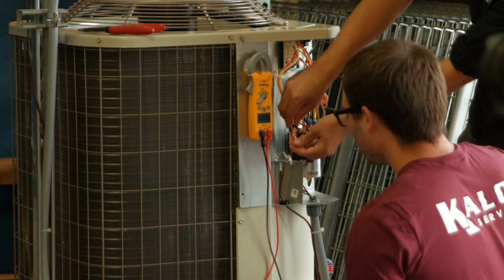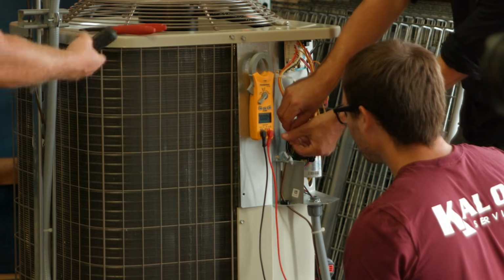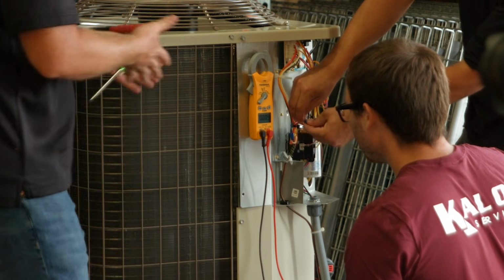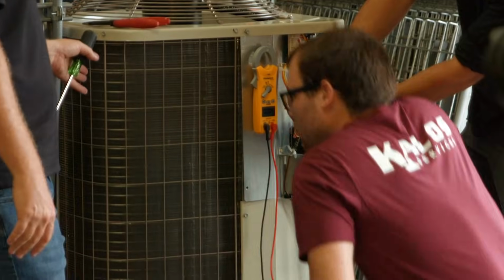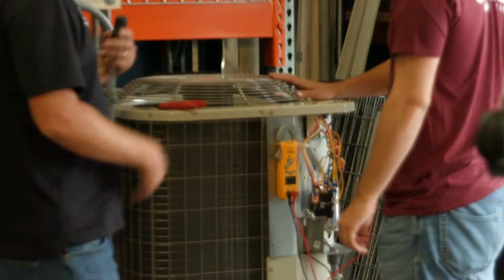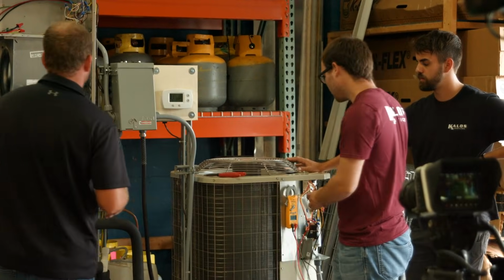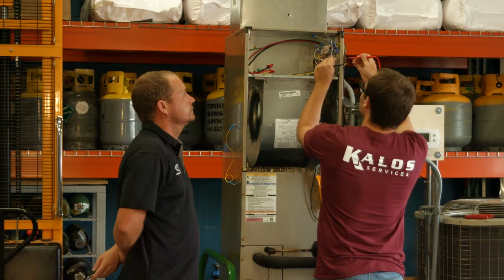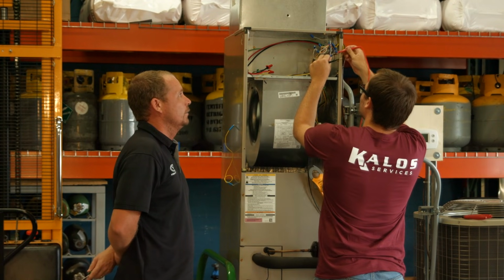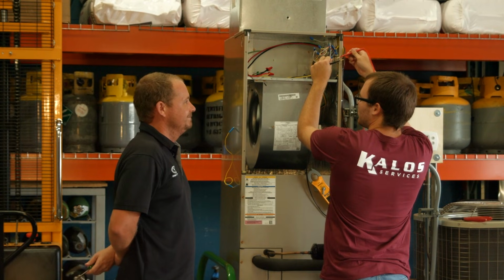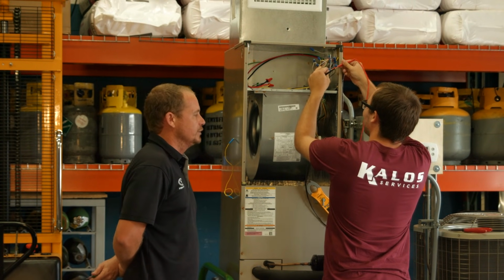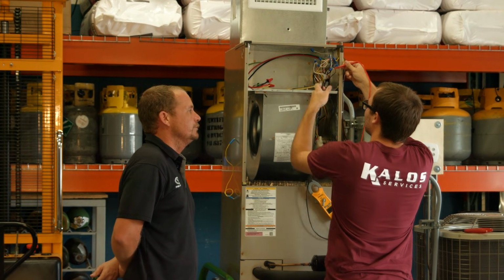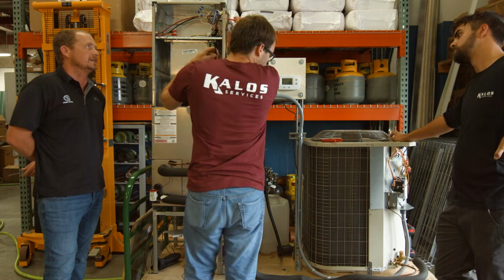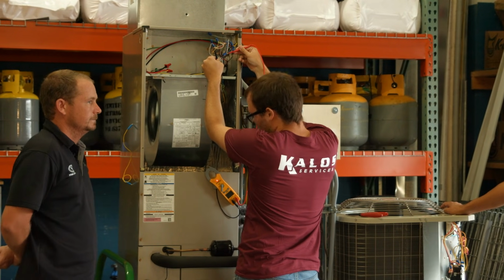When you're out at the condenser, this is where you would, because, to Eli's point, you're at the condenser, that's where you found out that it's running in heat. So you might as well check it there, exactly. Start wherever you are rather than running back and forth. Now again, whenever you're going to test within a wire nut, it's hard to trust. So you would want to check to another circuit too if you get a case where you're not measuring anything. Okay, so I am getting 24.